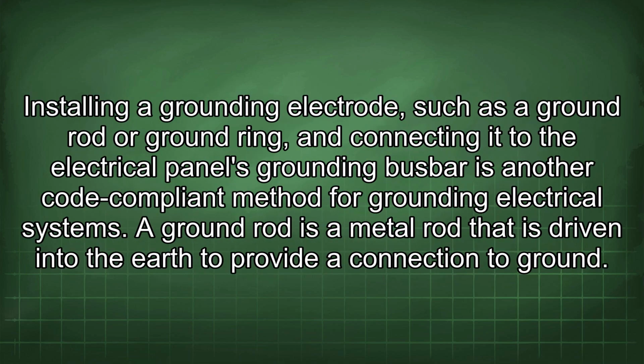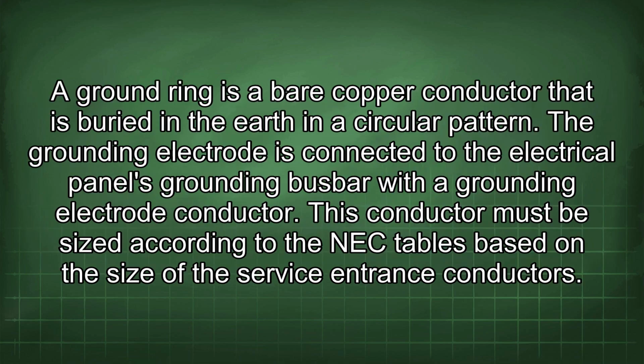Installing a grounding electrode, such as a ground rod or ground ring, and connecting it to the electrical panel's grounding busbar is another code-compliant method for grounding electrical systems. A ground rod is a metal rod that is driven into the earth to provide a connection to ground. A ground ring is a bare copper conductor that is buried in the earth in a circular pattern.